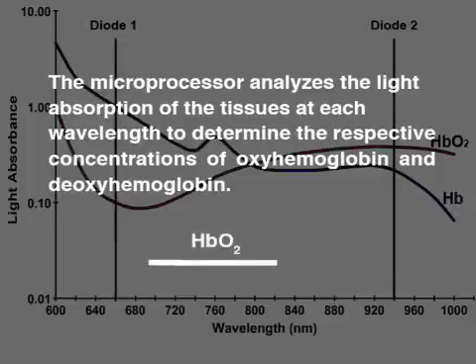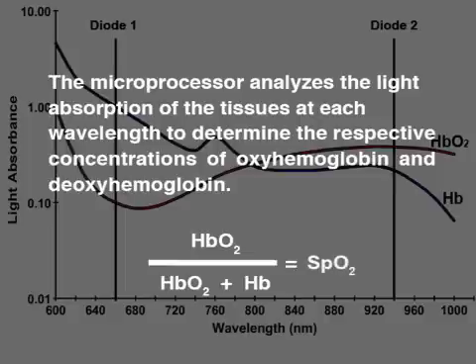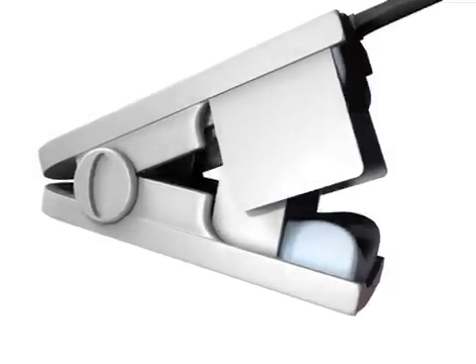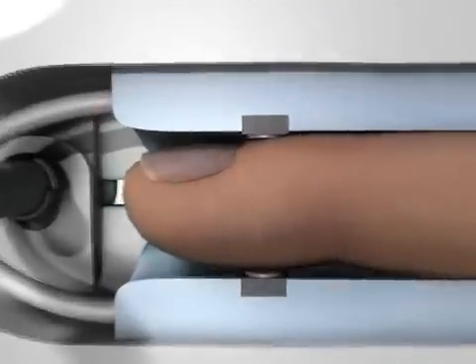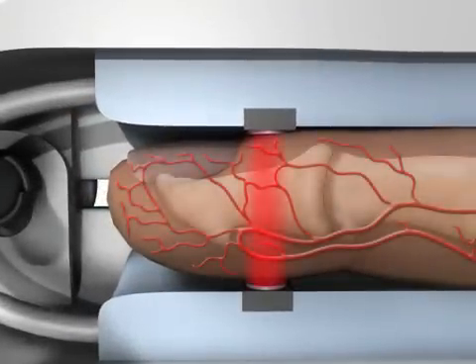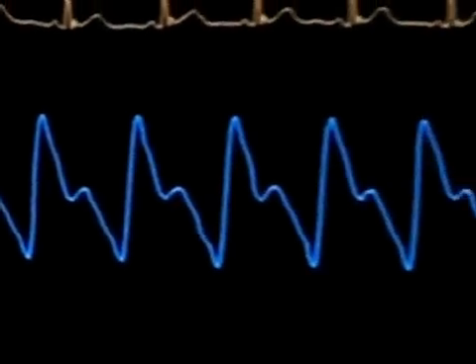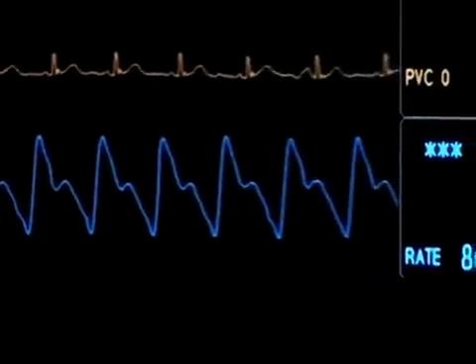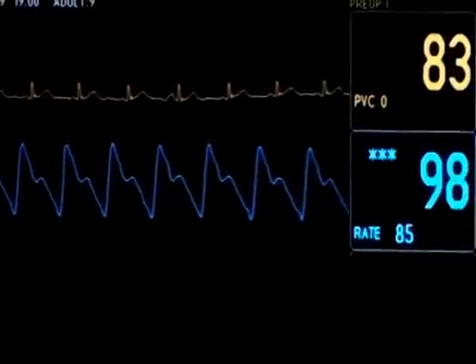The microprocessor divides the concentration of oxyhemoglobin by the sum of the concentration of oxy and deoxyhemoglobin to determine the arterial blood oxygen saturation, SpO2. The probe is positioned so that the photodetector and light-emitting diodes face each other, with layers of tissue between them. The photodiodes turn on and off several hundred times per second to record the light absorption during pulsatile and non-pulsatile flow. During pulsatile flow, the light absorption of arterial blood, background tissues, and venous blood is detected. During non-pulsatile flow, only the light absorption of background tissues and venous blood is detected. The microprocessing unit compares the light absorption during pulsatile and non-pulsatile flow to isolate the light absorption of arterial blood and thus determine the arterial blood oxygen saturation.